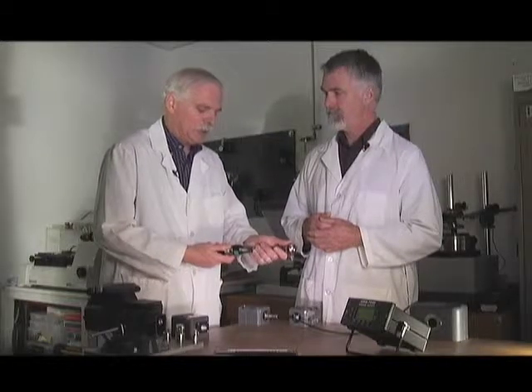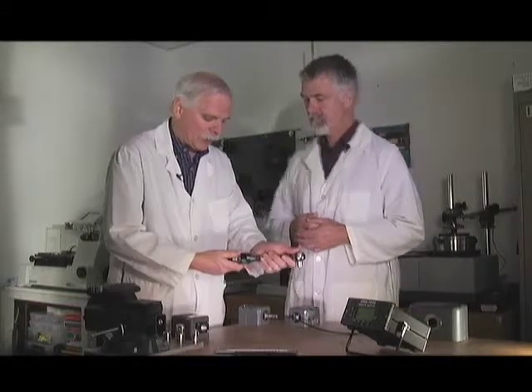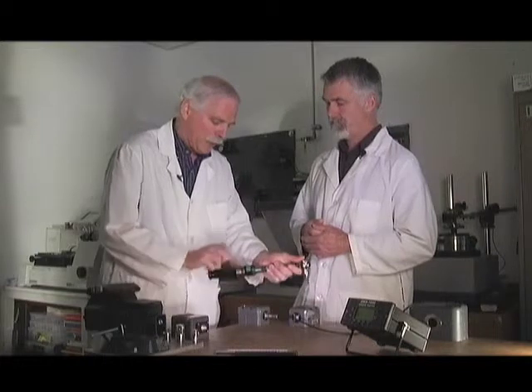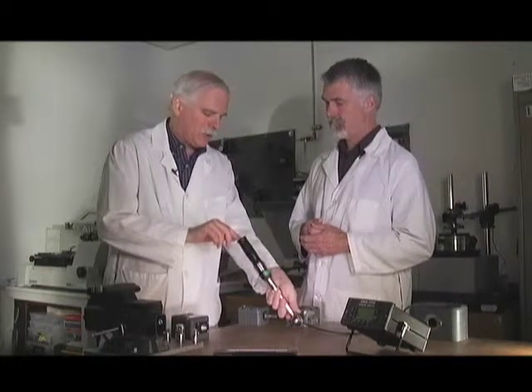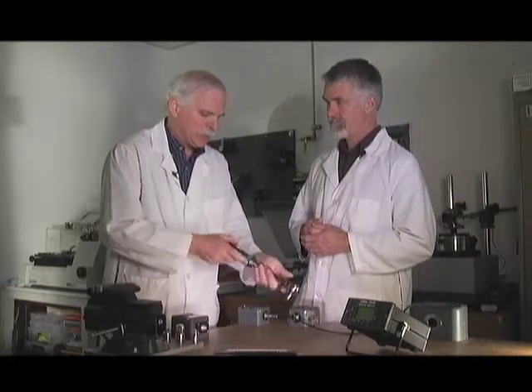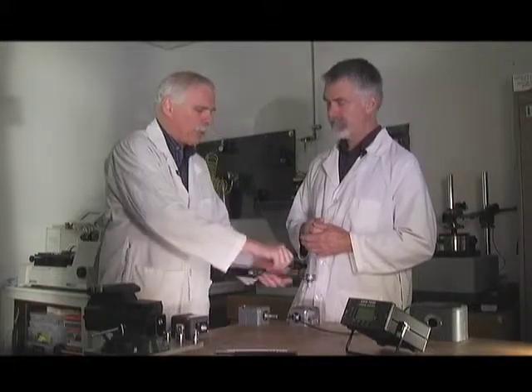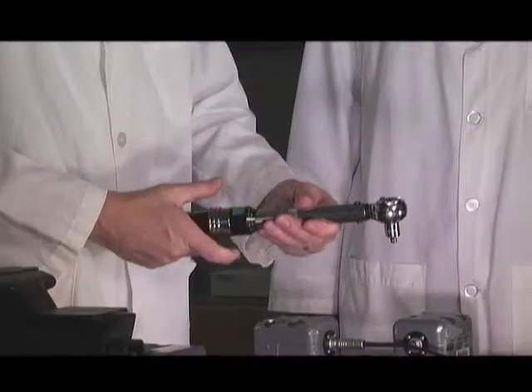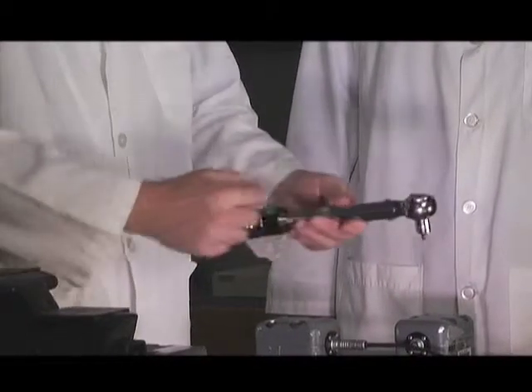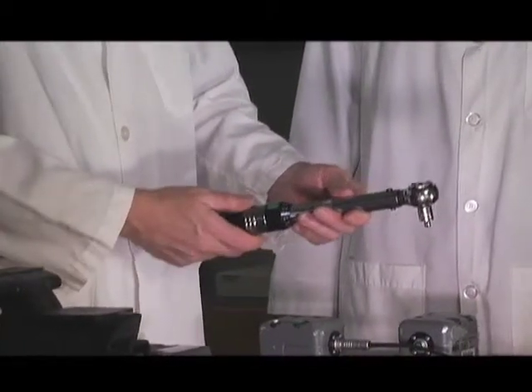Usually what you'll do is we will disassemble it part of the way, set it to a known low reading, then either up the shaft there's an adjustment screw. Sometimes they have it up here. That would be for the high range. We go back and forth. The main point to remember on these is to keep them clean, and if it's spring loaded, unwind it when you're done using it. Okay.